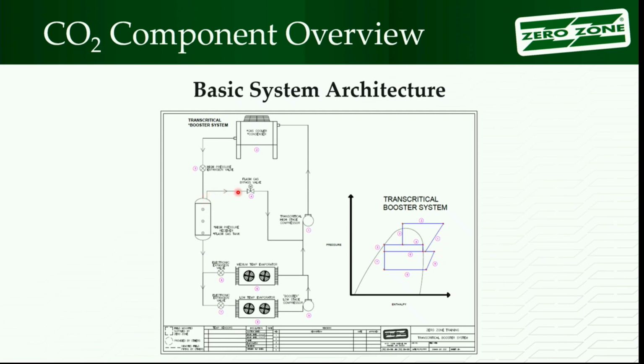And as I said, if I don't have that valve, that gas would go right back to that compressor. If that tank was the same pressure as a compressor, no flow through the evaporator. So that gas can go back through there. And then coming out of the tank, we're going to have liquid. The liquid's going to be just like any refrigeration system. It's going to feed an expansion valve. The expansion valve is going to go through the evaporators. Medium temp, it's going to go up to the high stage. Low temp, it's going to go over to the booster.